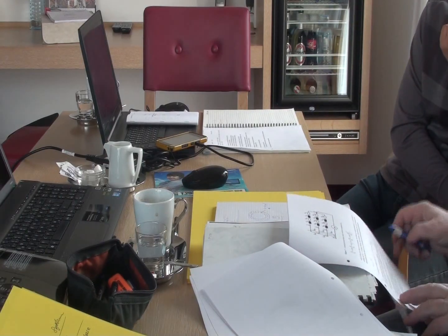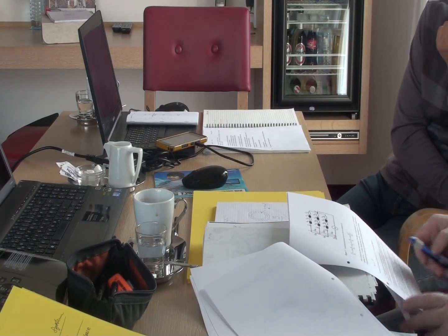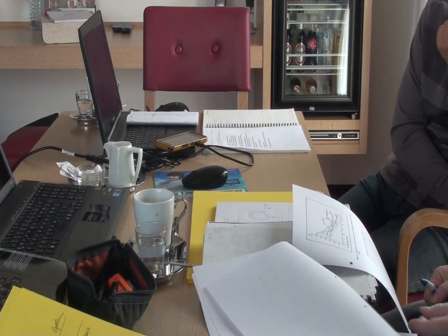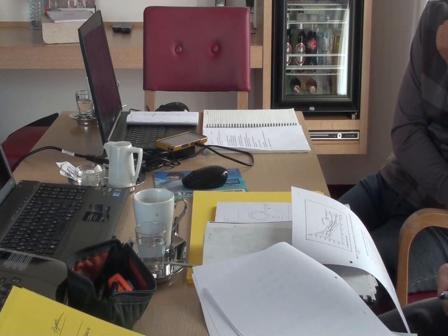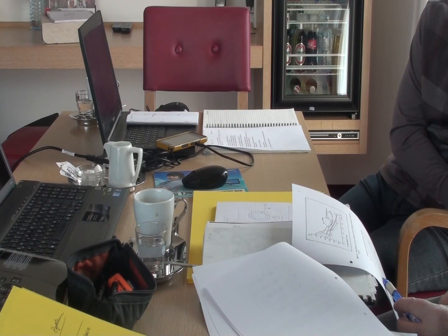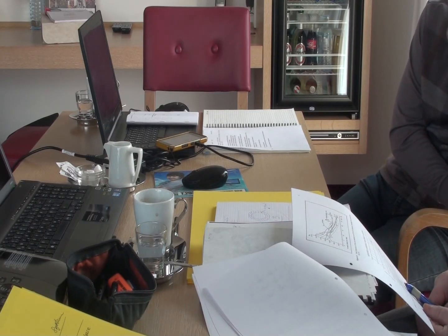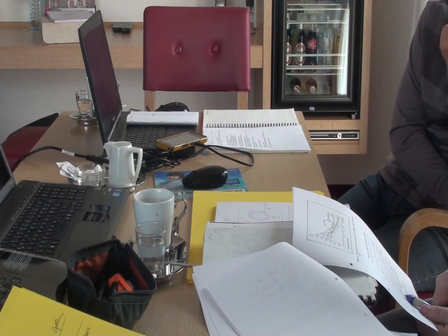And then Mr. Bowman, you know Mr. Bowman from Union Carbide, he has made many measurements and asked how is the additional increase of the reactance, the ratio between the operating and the short circuit reactance during furnace operation and at the working point. This is a cosinus of the phase. This is long arc, this is short circuit.